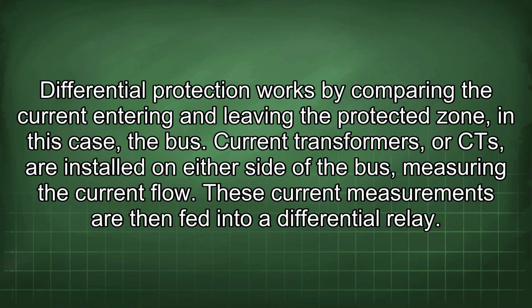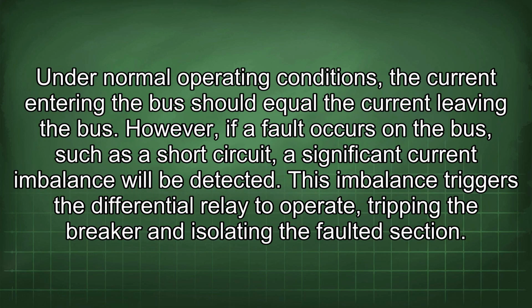Current transformers, or CTs, are installed on either side of the bus, measuring the current flow. These current measurements are then fed into a differential relay. Under normal operating conditions, the current entering the bus should equal the current leaving the bus. However, if a fault occurs on the bus, such as a short circuit, a significant current imbalance will be detected. This imbalance triggers the differential relay to operate, tripping the breaker and isolating the faulted section.